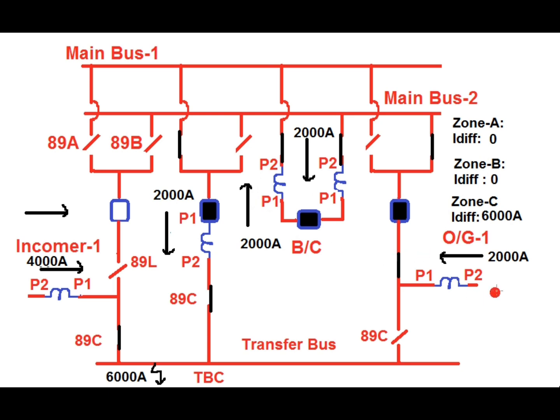For zone C during the fault: current through the incomer CT flows P2 to P1, which is the forward direction for zone C. The TBC CT current also contributes in the forward direction for zone C. The total zone C differential current is 6000 ampere. This triggers a trip signal based on the 89C status, causing the TBC breaker to trip and isolate the fault.